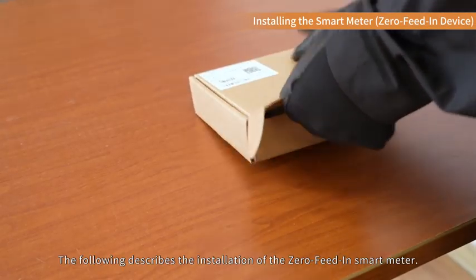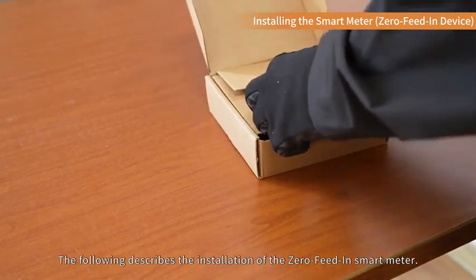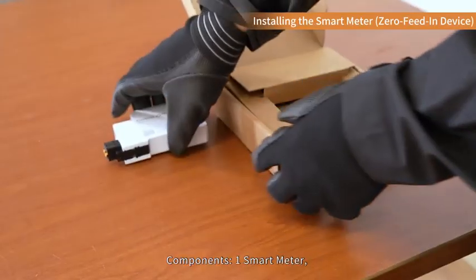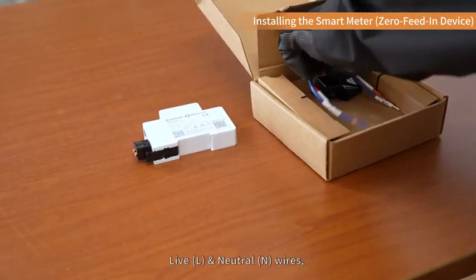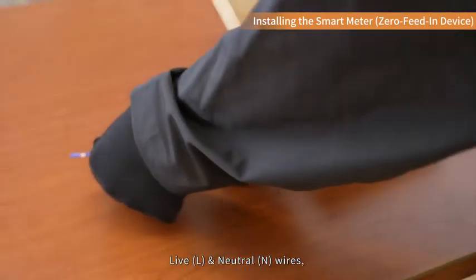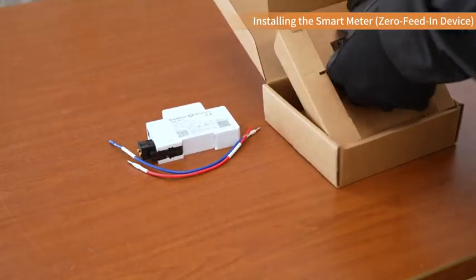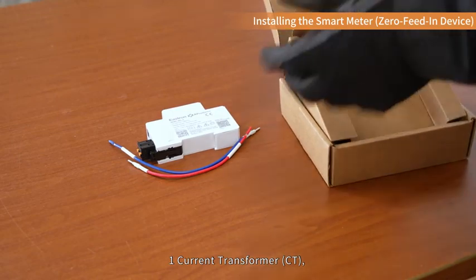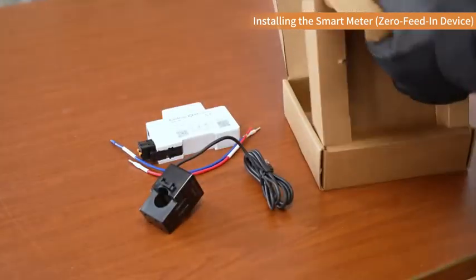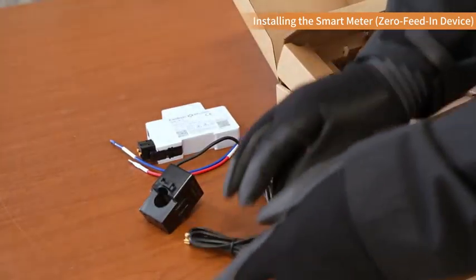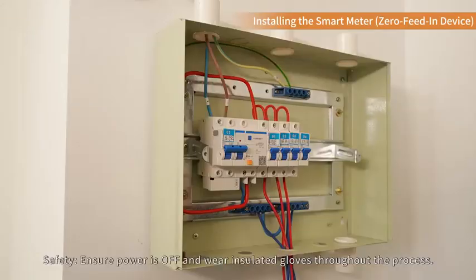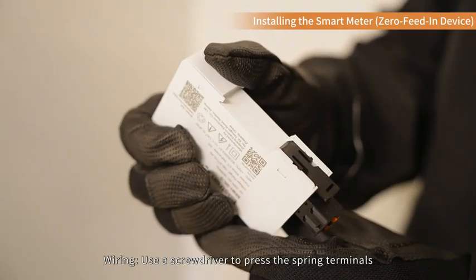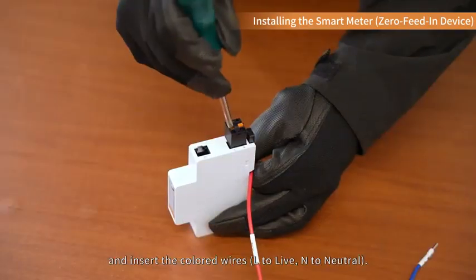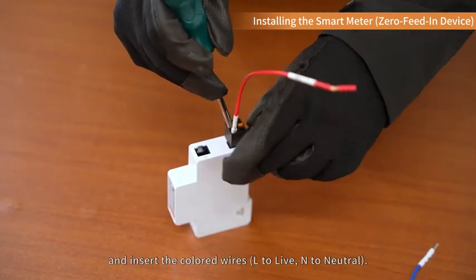The following describes the installation of the zero feed-in smart meter. Components: 1 smart meter, live L and neutral N wires, 1 current transformer CT, and 1 antenna. Safety: ensure power is off and wear insulated gloves throughout the process. Wiring: use a screwdriver to press the spring terminals and insert the colored wires, L to live and N to neutral.